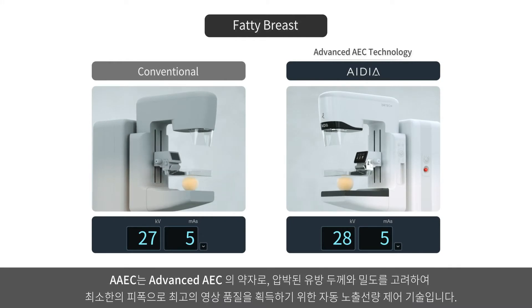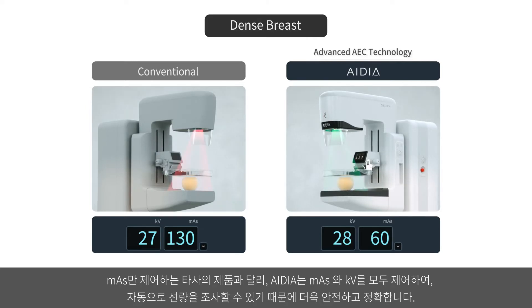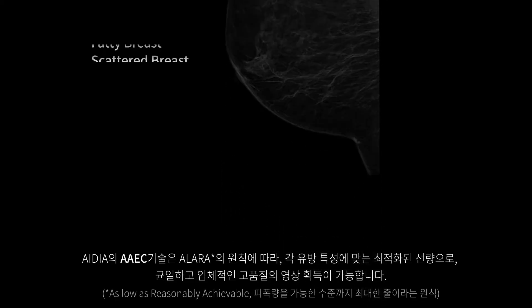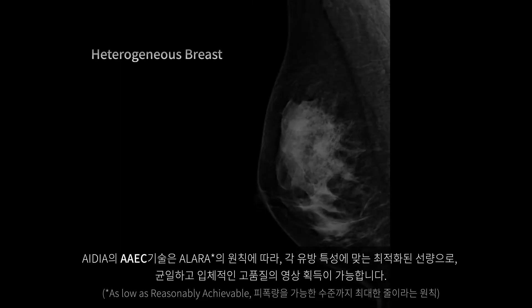AIDIA's advanced AEC is differentiated from others that only adjust the mAs settings for different breast types. AIDIA's AAEC exposes the right amount of radiation by controlling both the kV and mAs, calculating the patient's breast thickness and density, ensuring consistent high-quality images while maintaining optimized low-dose.